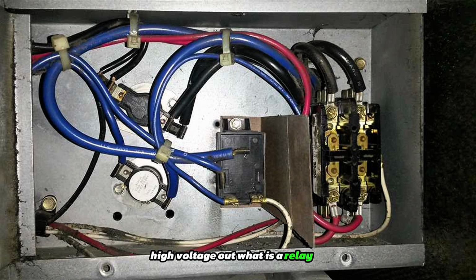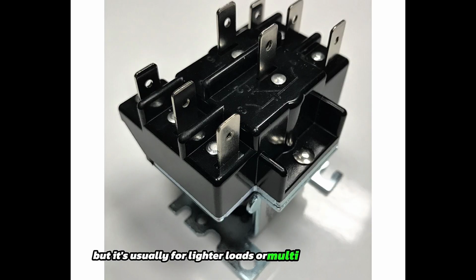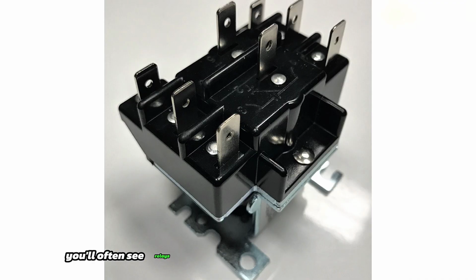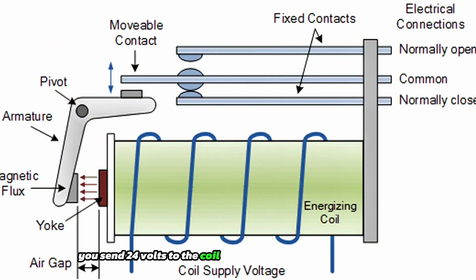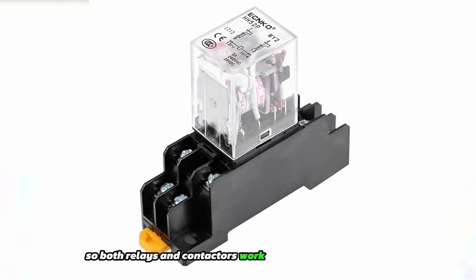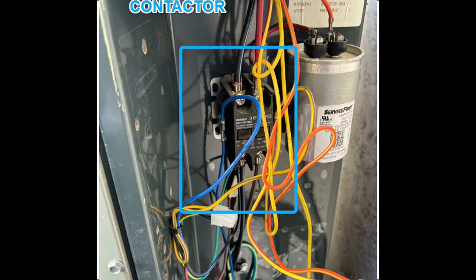What is a relay? A relay works the same way, but it's usually for lighter loads or multi-speed circuits. You'll often see relays inside the air handler, used to energize PSC blower motors, electric heaters, or secondary controls. You send 24 volts to the coil, and it switches either 120 or 240 volts on the other side. So both relays and contactors work by the same principle. A small control signal moves a magnetic coil, which closes or opens a separate electrical path.